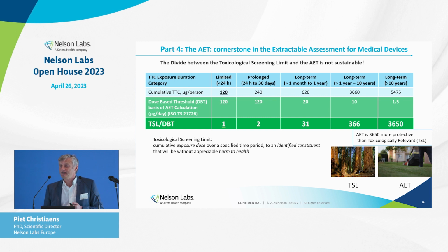Although I can understand that the AET really needs to be lower, factor 10, factor 100, whatever. There are reasons to go lower. Cohorts of concern can be a reason. Grouping of compounds to do a tox assessment can also be a reason. But having this kind of divide between a toxicological screening limit and the AET is not sustainable. Something will need to develop, something will change, most probably, to bring that AET level up so that it becomes manageable. However, the ISO 10993-17 is in its FDIS phase. Normally, content-wise, nothing will change anymore. It was introduced by the FDA, so you would expect that they accept it. So something is not right there.